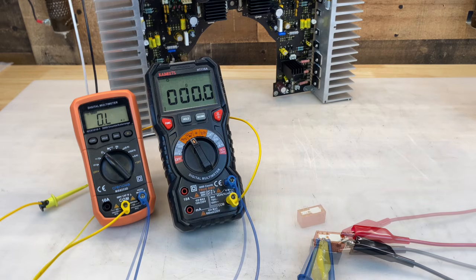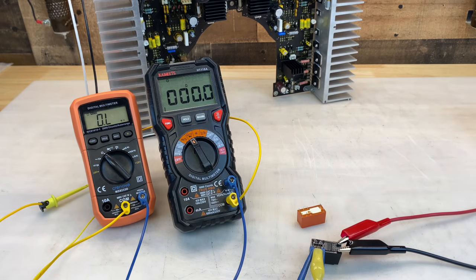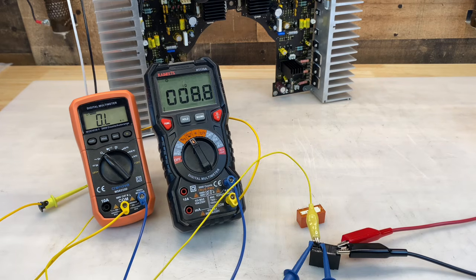Just like that. This is RY3. We have the same starting conditions. I'll apply 12 volts to the coil now. We can hear it engage. One set of contacts does flip from short to open, but the other never flips from open to short. We do indeed have a bad relay. I'll check the other side for completeness. The other side shows the same fault. This relay is no bueno.